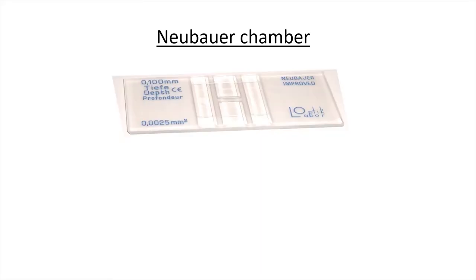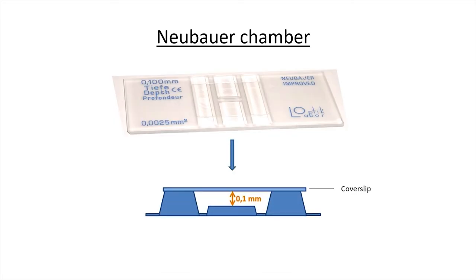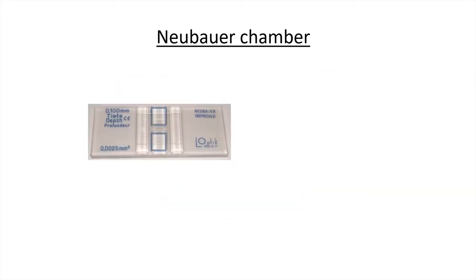The height of the lateral zone of the chamber differs by 0.1 millimeters in height from the central zone. So if we look at the chamber in profile, we will detect this difference in height. An important fact to take into account when calculating the number of cells.